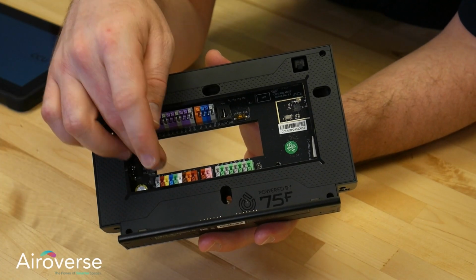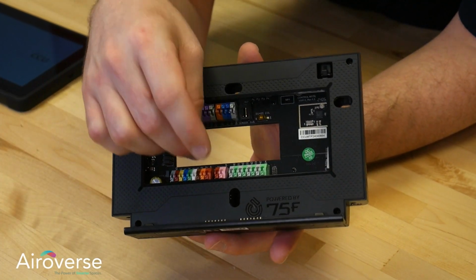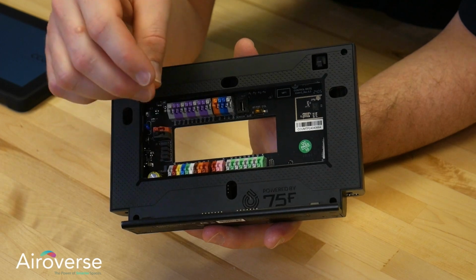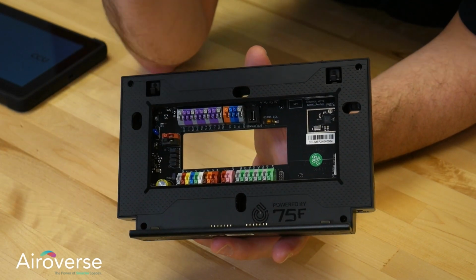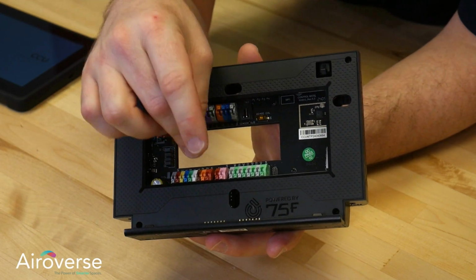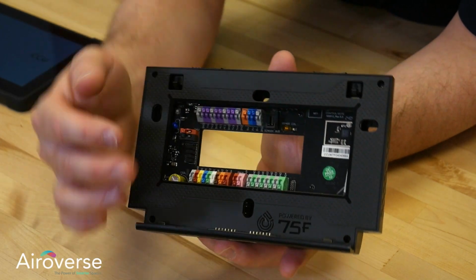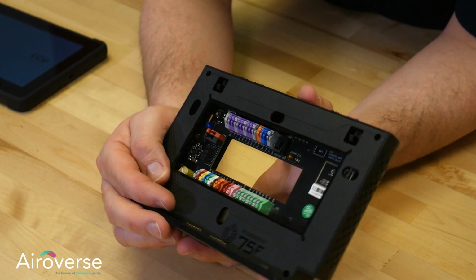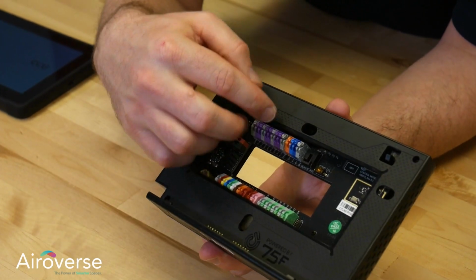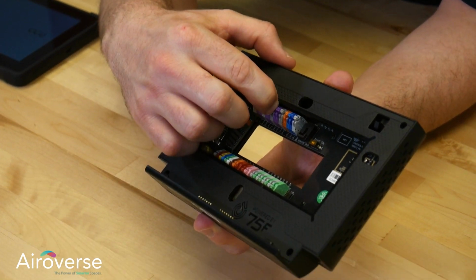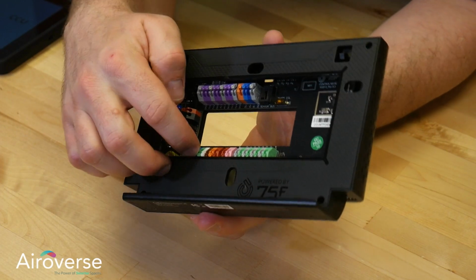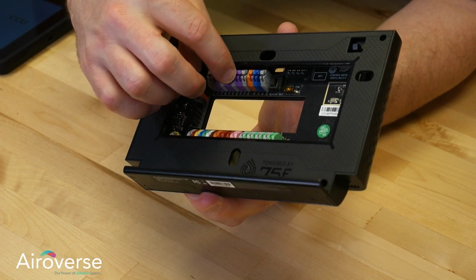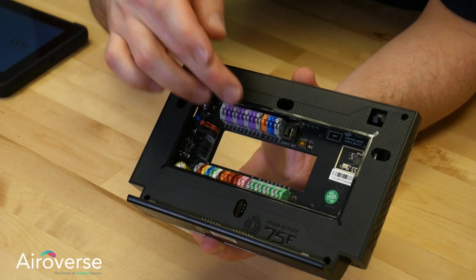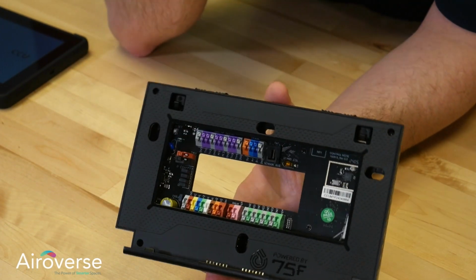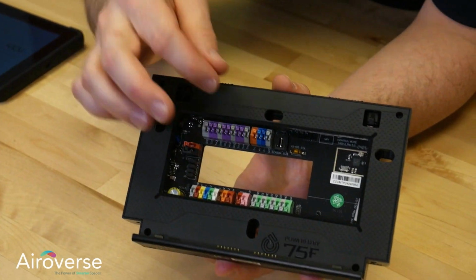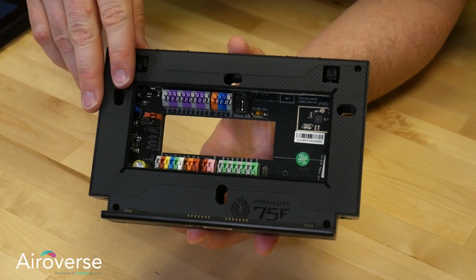When you're actually terminating the wires in here, typically if you're using solid core wire, these are poke-in style connectors. You can take the wire, strip it back about 1/2 inch, and just poke it into the hole. If you're using stranded, which is more common with the thermistors, what you can do is depress the top. There's a little, what looks like a button on the top of each one. You can depress that and it loosens up the spring inside so that you can insert your wire, and then you release the spring and it gets a nice tight hold.